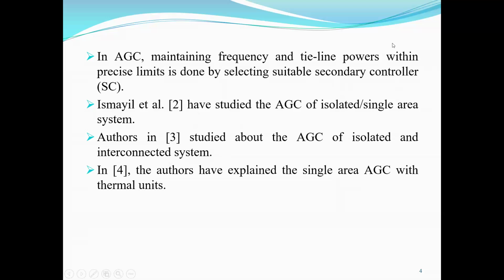The primary controller mechanism is provided by the governor of the given turbine. But with the governor of the power plant, whether thermal or hydro, you may not get the frequency variation down to zero. If we select the secondary controller, however, it is quite possible to achieve zero frequency deviation. We'll see shortly in the lecture the impact of this secondary controller, and what happens if there is no secondary controller.